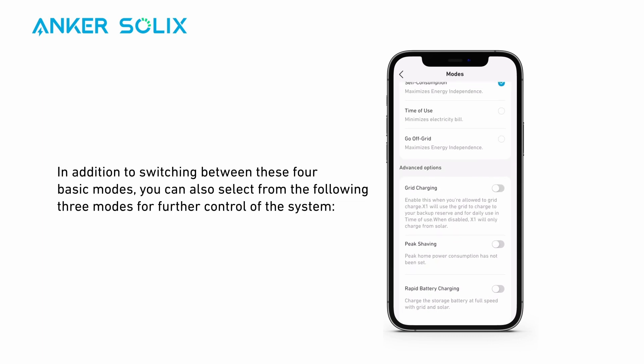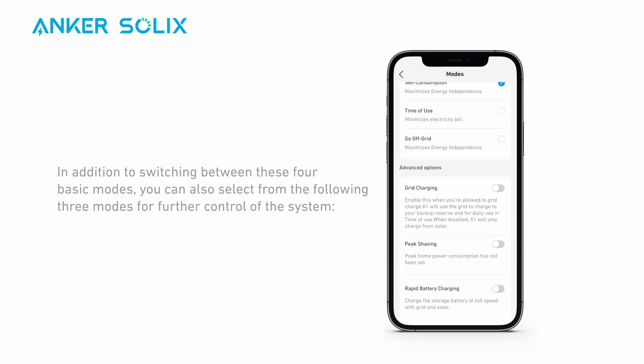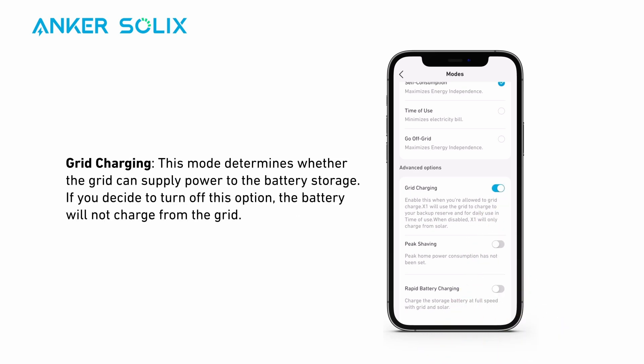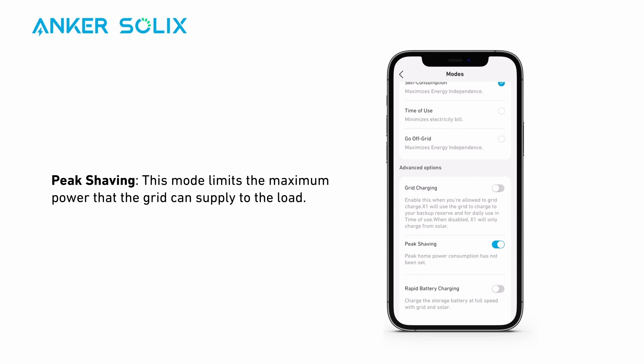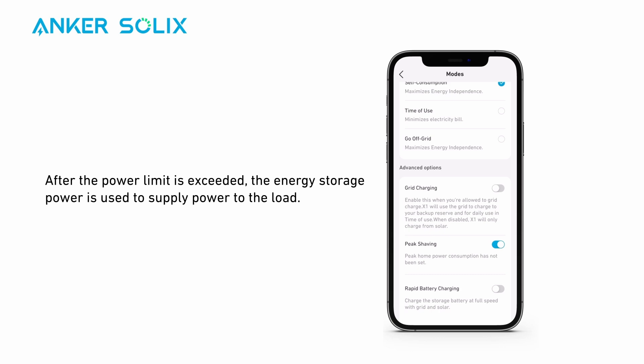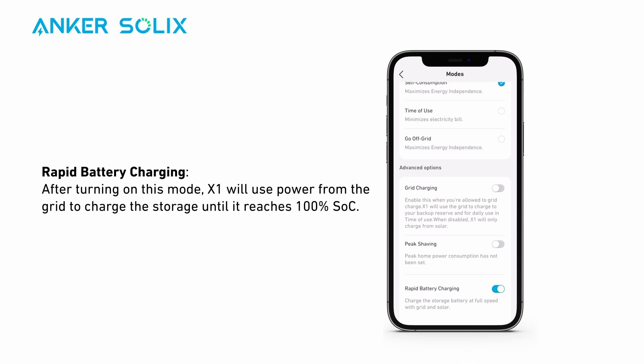In addition to switching between the four basic modes, you can also select from three additional modes for further control. Grid Charging determines whether the grid can supply power to the battery storage; if you turn off this option, the battery will not charge from the grid. Peak Shaving limits the maximum power that the grid can supply to the load; after the power limit is exceeded, the energy storage power is used to supply power to the load. Rapid Battery Charging, when turned on, will use power from the grid to charge the storage until it reaches 100% SoC.